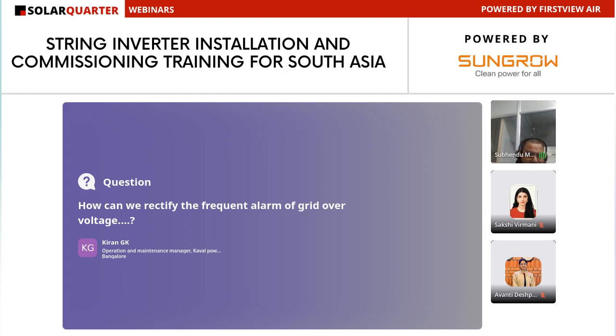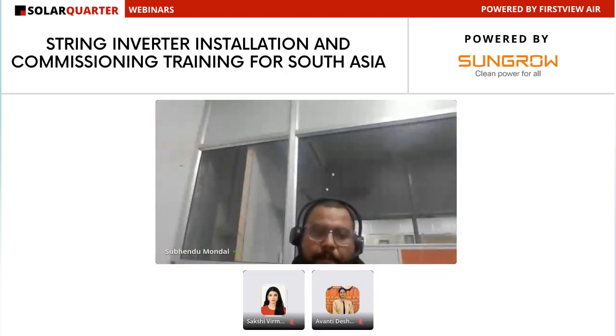How can we rectify the frequent alarm of grid over voltage? We have some grid over voltage settings. First, we have to check whether the settings are proper or not, and whether the inverter setting is according to the grid or not. We have to check that the AC setting is according to the grid or not. You can check using the iSolarCloud app.